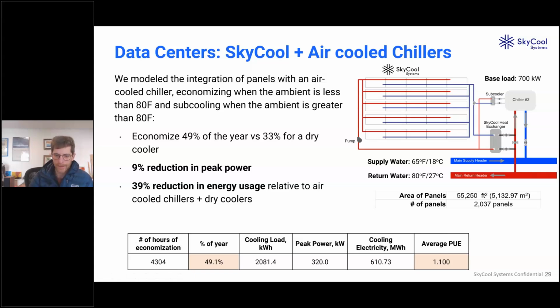1.1. And so data centers are different from these cooling systems and the refrigeration systems just because they are much bigger. So this is for a 700 kilowatt cooling load at a 1 megawatt facility. But you essentially need a lot more panels. It's nominally 2,000 panels in this case versus the 80 panels I mentioned for the supermarkets previously.